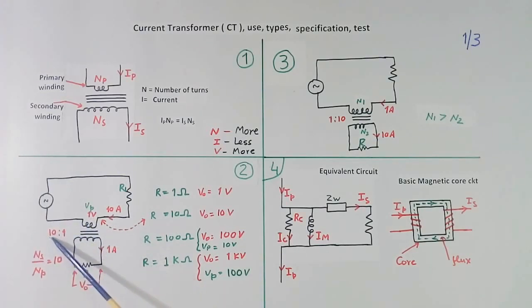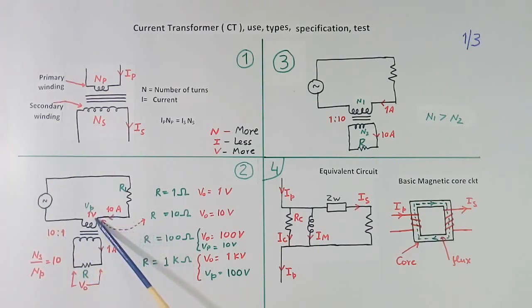Here we have a CT of ratio 10 is to 1. 10 is to 1 means if primary current is 10 ampere, secondary current will be 1 ampere. And turn ratio will be reversed 10 is to 1. Secondary turn will be more. If turn is more, current is less. Because here current is less, here turns are more. And we have connected a resistor across secondary. Now when 10 ampere is flowing here, 1 ampere will flow here. Suppose we connect R equal to 1 ohm. So 1 ampere into 1 ohm is equal to 1 volt.